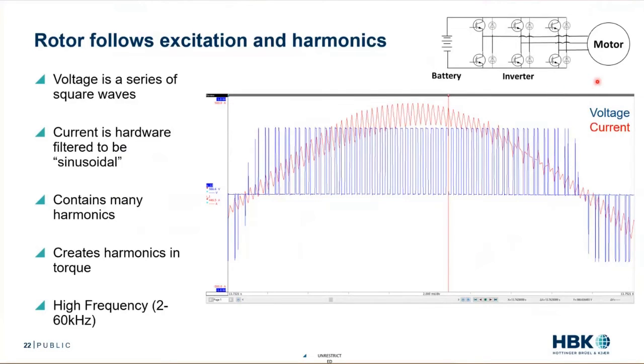These switches are either on or off — voltage on for a period, voltage off for a period. On the screen in the middle, the blue waveform is our voltage and red is our current. On the left-hand side we have very short pulses; as we go toward the middle, pulses get progressively longer; then toward the right, they get progressively shorter. The motor acts as an electrical filter — an inductor — taking that voltage waveform and filtering it into that red current. While the switch is on, we're charging that current; while off, we're discharging it, producing a spiky but recognizable sine wave.